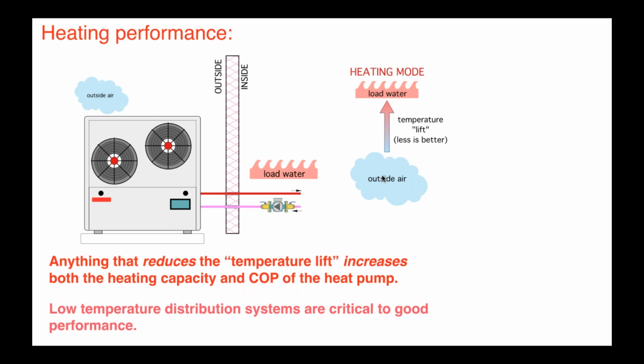In this case, it's the change in temperature between the outdoor temperature and the water temperature that's leaving the heat pump going off to your load. We call that the temperature lift. Remember, there's a lot of heat in outside air, even at low temperatures, but we have to lift the temperature of that heat to a value that we can then use to heat the building.